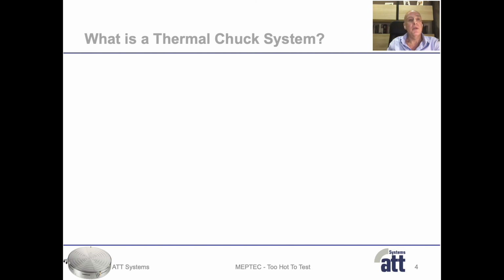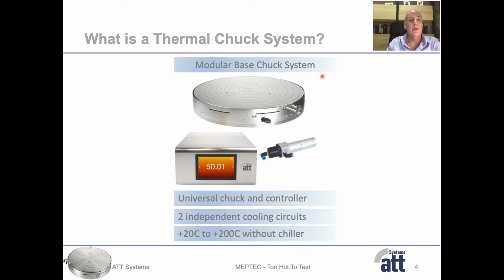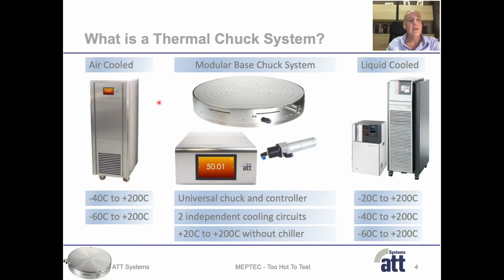Let's briefly recap. What is a thermal chuck system? The thermal chuck system consists of the thermal chuck, the temperature controller, and maybe a cooling booster for controlled ambient up to plus 200 degrees applications without a chiller. For cold probing, there are two options: air-cooled chillers and liquid-cooled chillers. Both methodologies offer different chiller configurations for different temperature ranges, maybe minus 40 degrees C or minus 60 degrees C. Ideally, the chuck and the controller can be used for both methodologies, air-cooled and liquid-cooled, for highest operational flexibility.